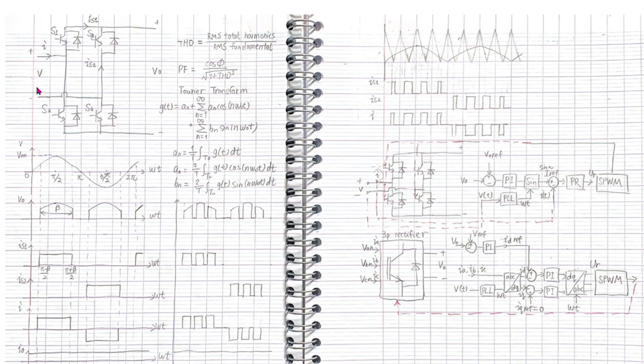Normally, the power factor is the cos phi. Phi is the angle between voltage and current. This is only applicable when both the voltage and current are sinusoidal. Distortion power factor is the cos phi divided by root of 1 plus THD squared. THD is the total harmonic distortion. When THD is high, we get a low power factor.